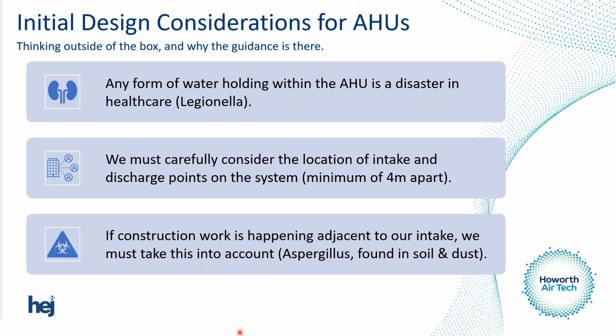Construction work happening on our sites is another factor. We need to consider where the intake section is, because aspergillus is a risk from dust. If there's construction going on, like demolishing a multi-story car park, and there's an air handling unit nearby supplying air into an intensive care unit, high dependency unit, or special care baby unit, these are things we must consider. If there's a risk, it's up to the ventilation safety group and the authorising engineer for Vent to help come up with a solution to mitigate the problem.